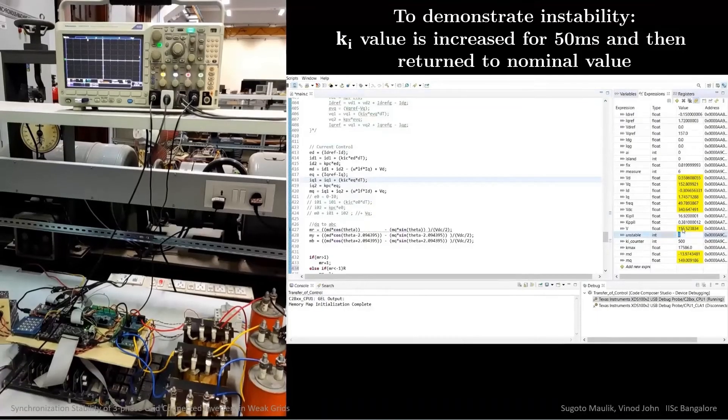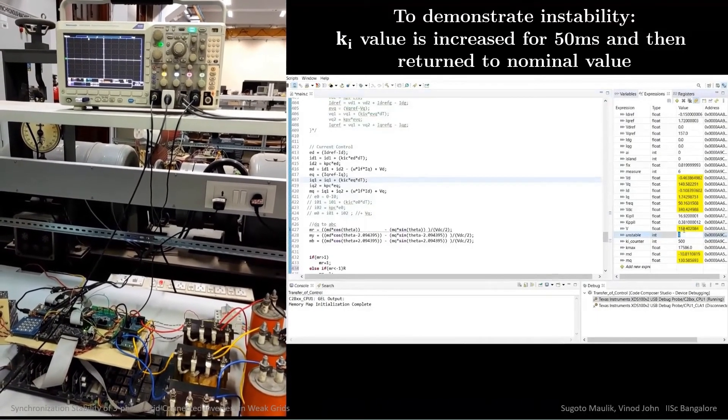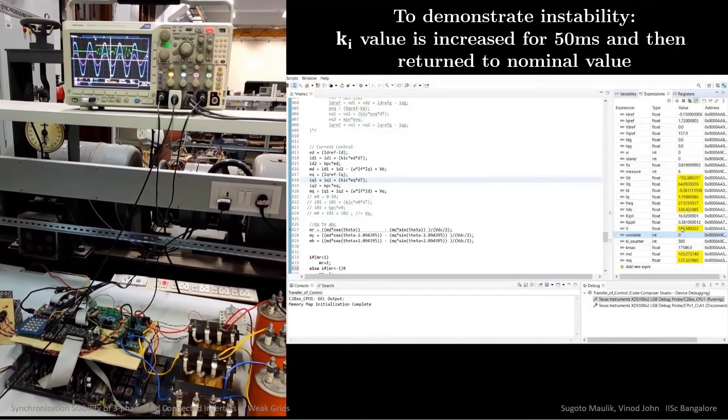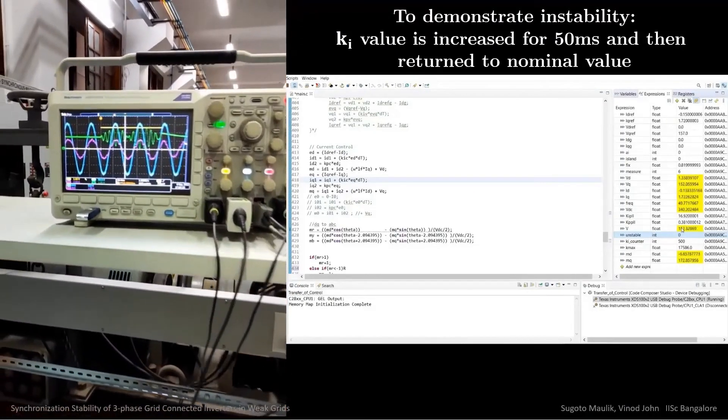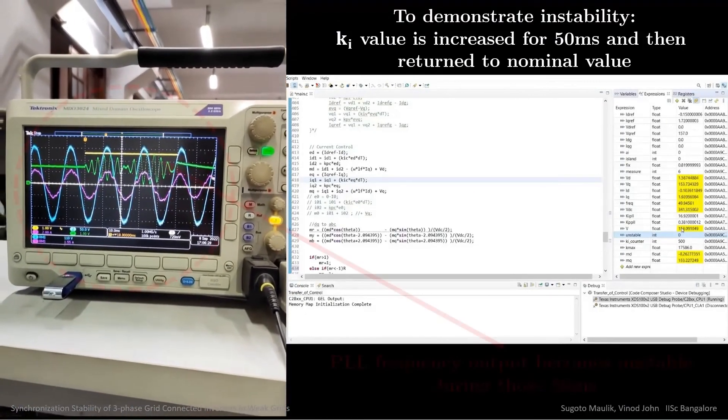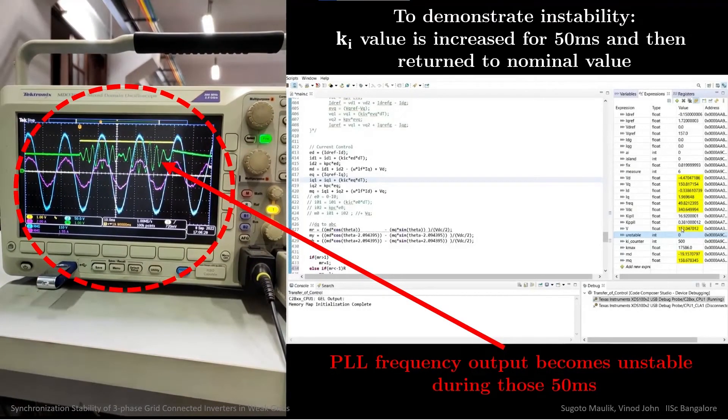For real-time demonstration of this instability, the PLL's KI value is increased for 50 milliseconds while the converter is running in grid feeding mode. The destabilizing impact of this increased KI is evident from the oscilloscope plot of the frequency output.